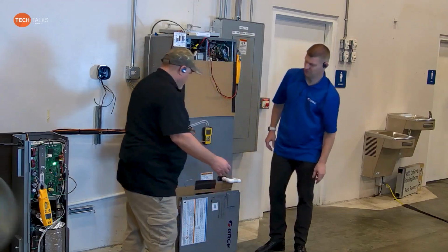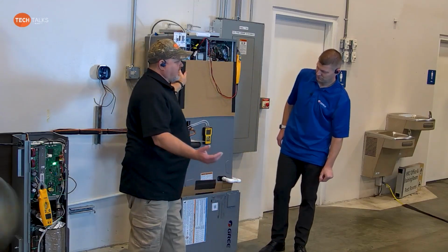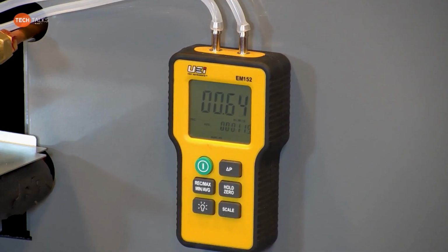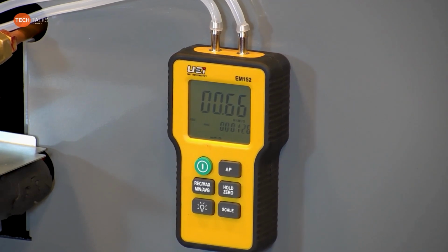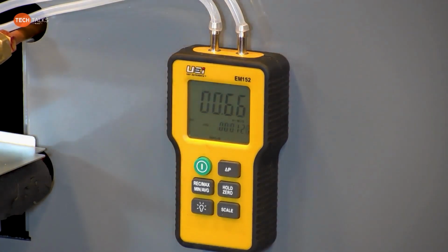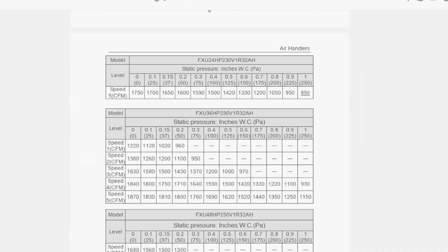I'm going to tell you guys, this just kind of gives you the concept behind it. When you don't have a ducted pressurized system, this is not the same world. It really isn't. When I set that blower profile on speed 4, or speed 5 is what we set it for, at 0.5 total static, I should be moving 1620 CFM.